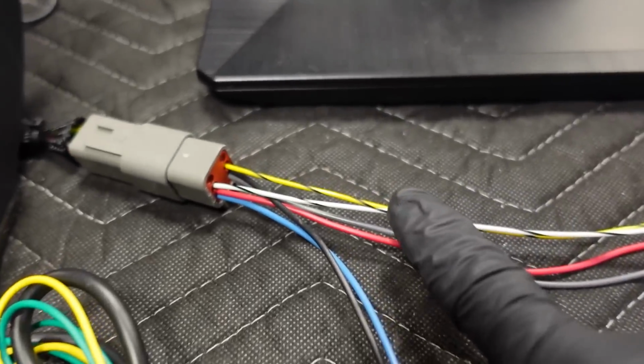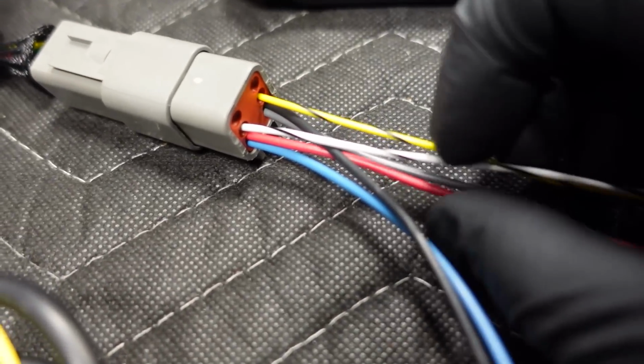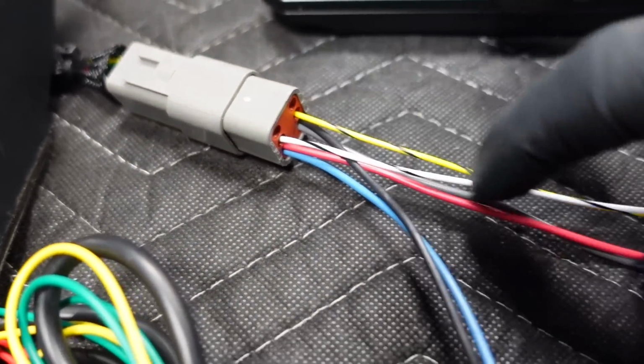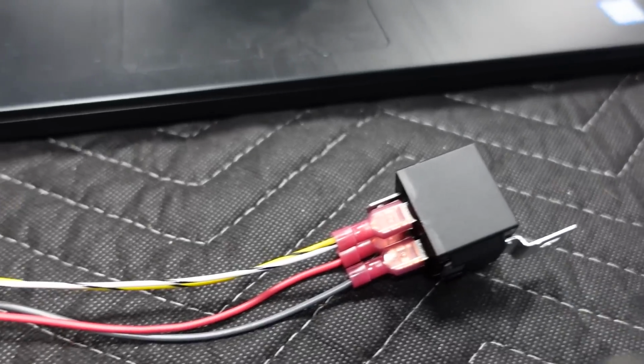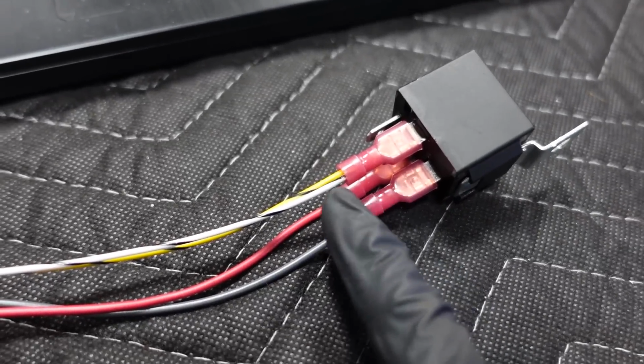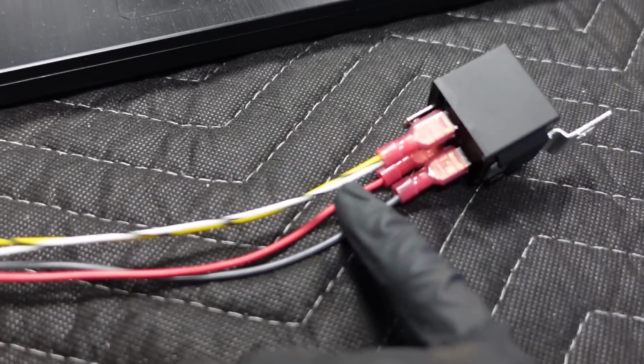When I do this, one of these, white with black, is a ground that gets sent to the coil of this relay, and the ground is on my common, with the relay in normally closed mode when I don't have this switch in drive or reverse.